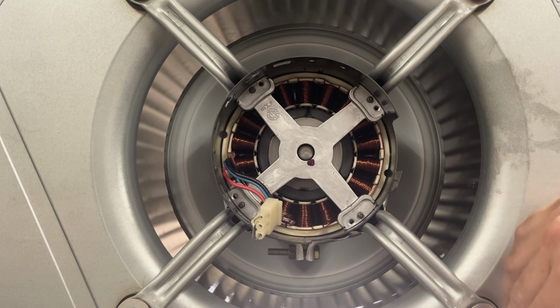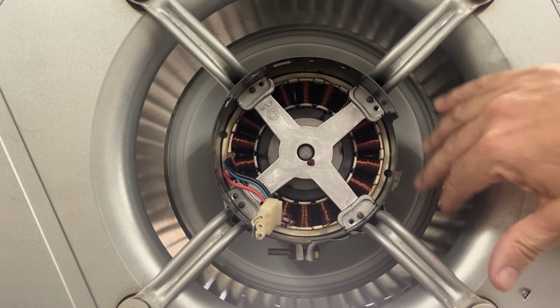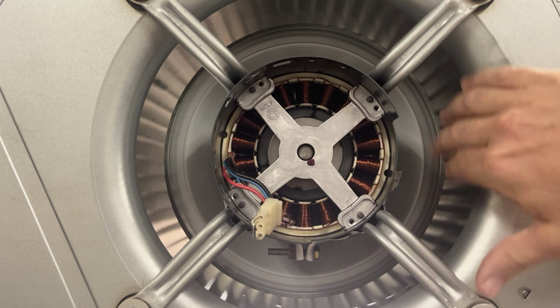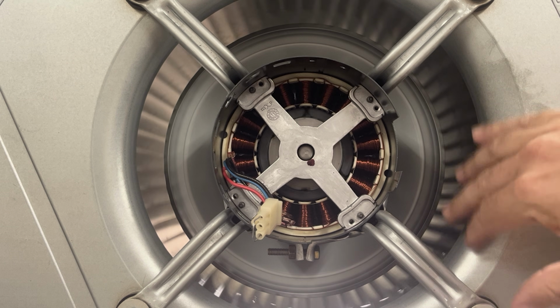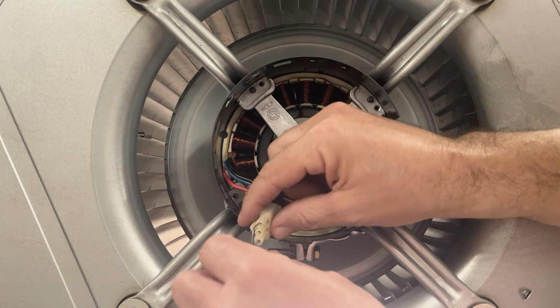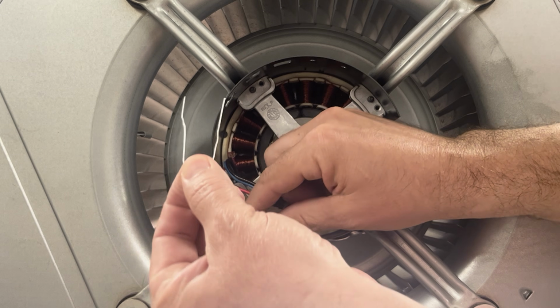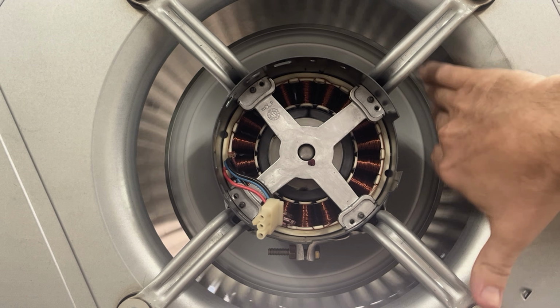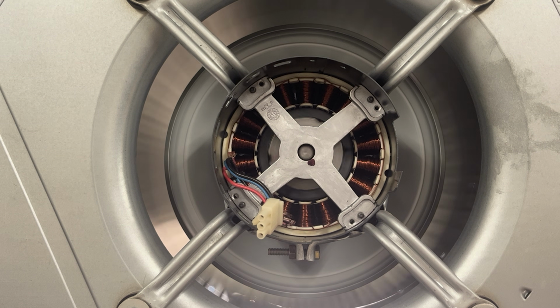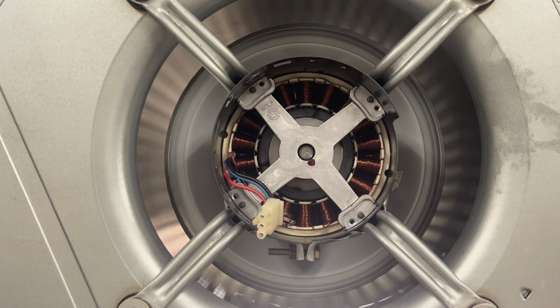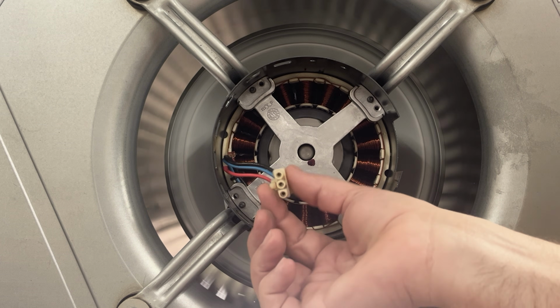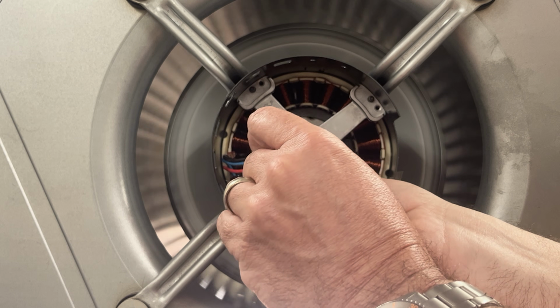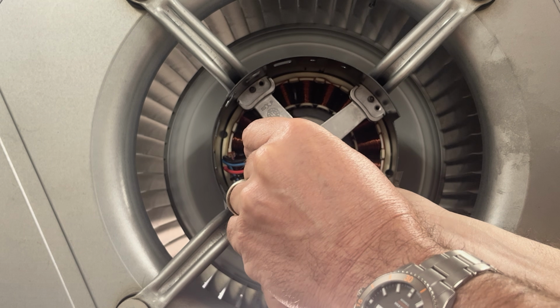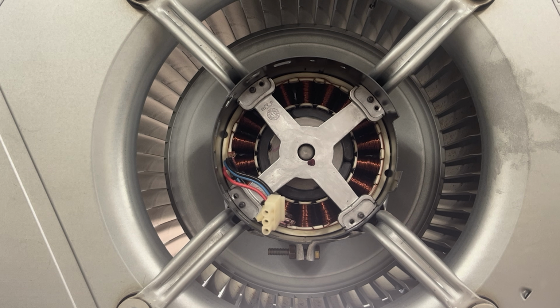And as you can see here, I really have to try to turn this thing. And so I'm getting a lot of resistance there, which says a lot about this motor. So this motor is good. And again, I'm going to go ahead and pull this back out and just show you, it's still spinning. It's not stopping. The moment I put this in here, as you can still see it spinning here, it immediately stops. And so that's a good motor, so I would know that I have a bad module.